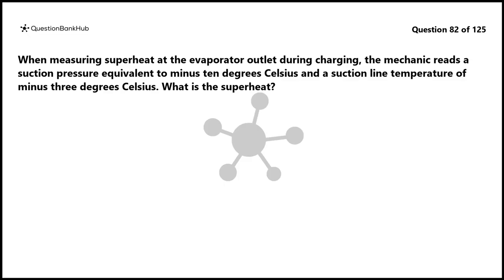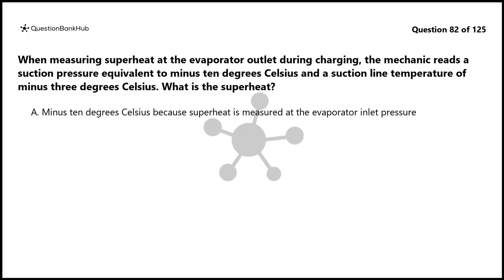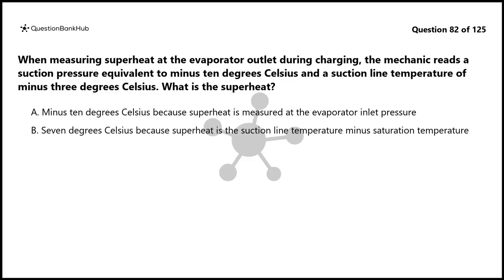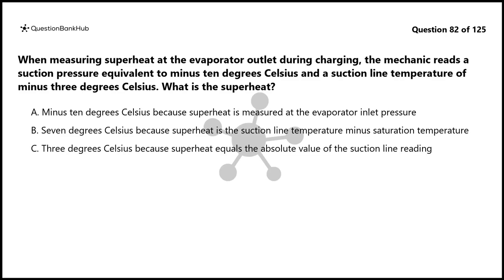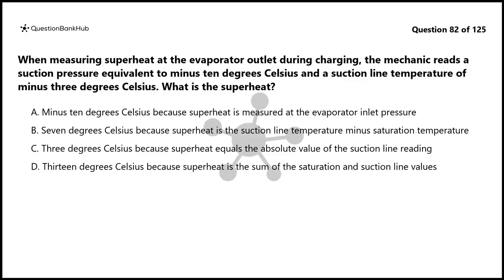Question 82. When measuring superheat at the evaporator outlet during charging, the mechanic reads a suction pressure equivalent to -10 degrees Celsius and a suction line temperature of -3 degrees Celsius. What is the superheat? A. -10 degrees Celsius because superheat is measured at the evaporator inlet pressure. B. 7 degrees Celsius because superheat is the suction line temperature minus saturation temperature. C. 3 degrees Celsius because superheat equals the absolute value of the suction line reading. D. 13 degrees Celsius because superheat is the sum of the saturation and suction line values.